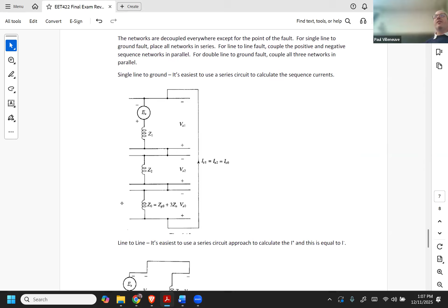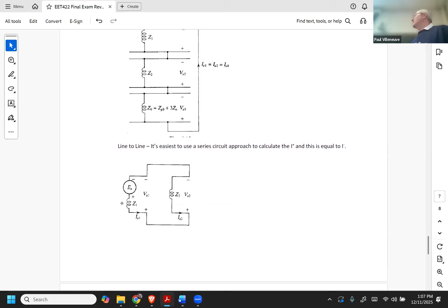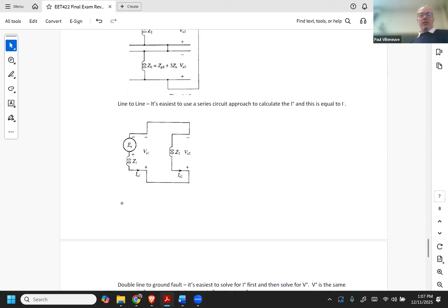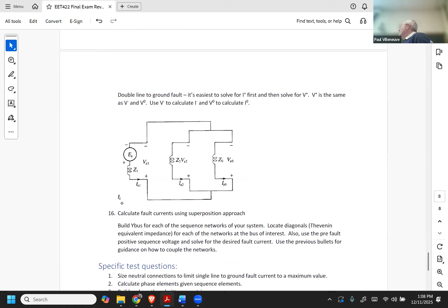For a single line to ground fault, take all three sequence networks and put them in series. For a line-to-line fault, take positive and negative sequence, no zero sequence since there's no connection to ground and no ground fault current, and connect them in parallel. For a double line to ground fault, put all three networks together in parallel and do the calculations.